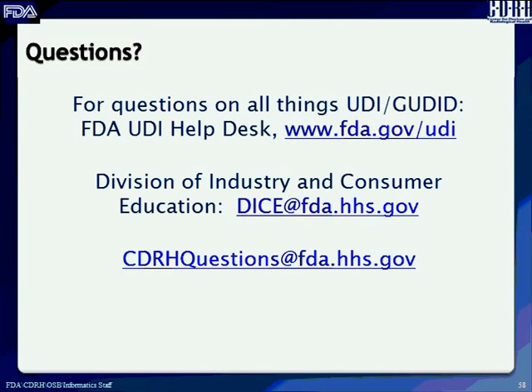The listing number is a number that's assigned by the FDA. There is a regulation under the registration listing regulation. All establishments must be registered, and the devices must be listed prior to being commercially distributed. The listing number may contain multiple device records, so a single listing may map to multiple DI records. I don't know how to explain the link between listing and GMDN except to say that the GMDN and the FDA preferred term code are both higher level categorization of devices.